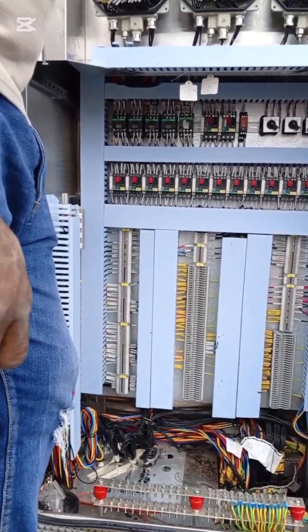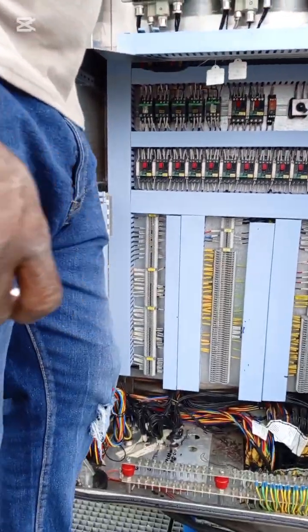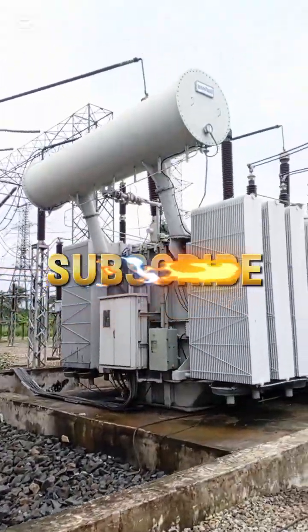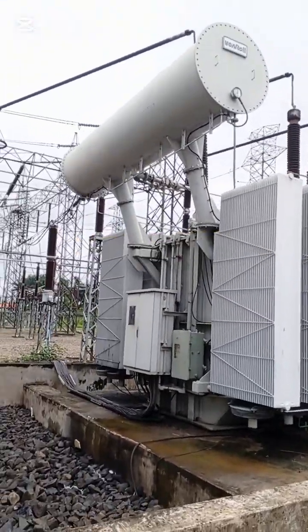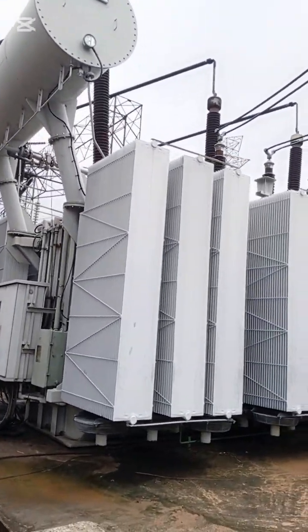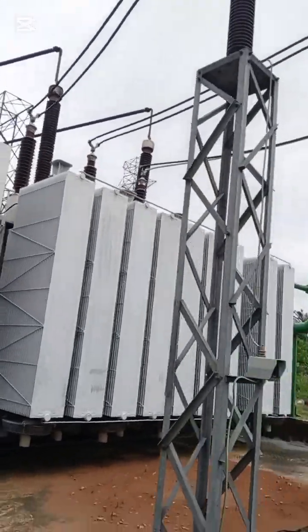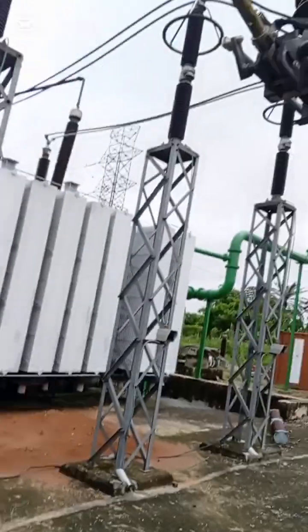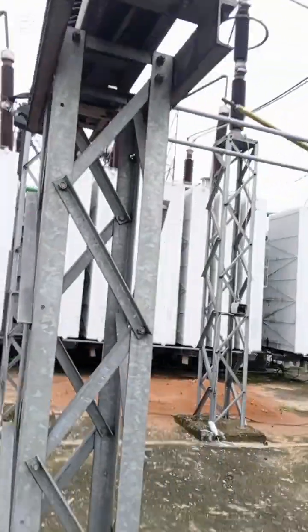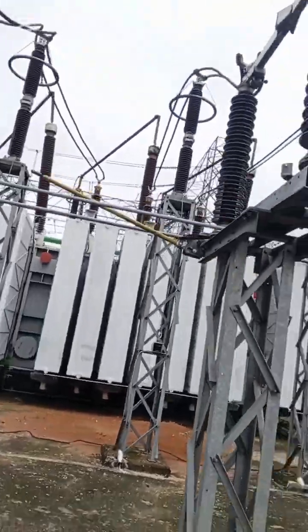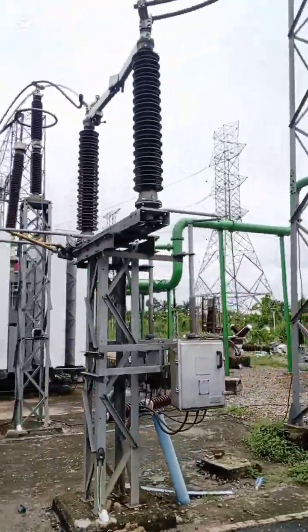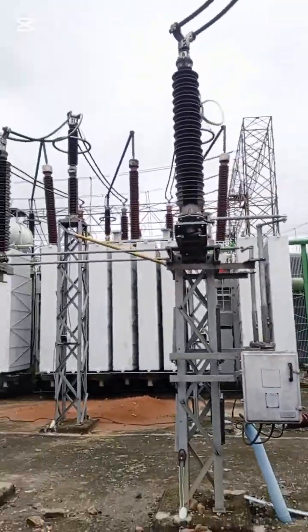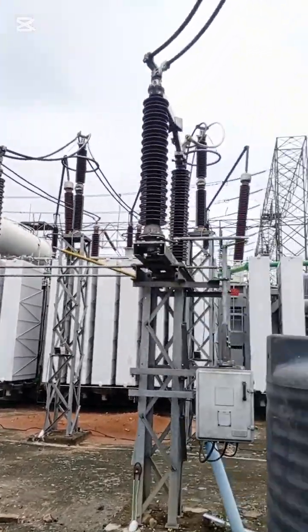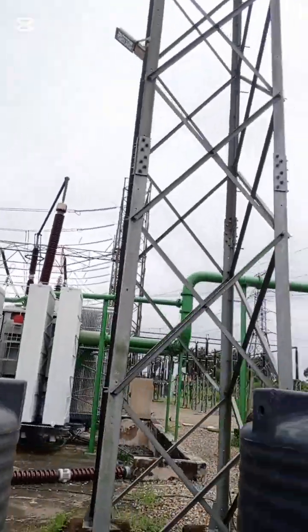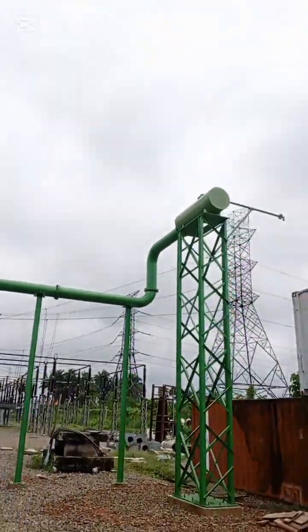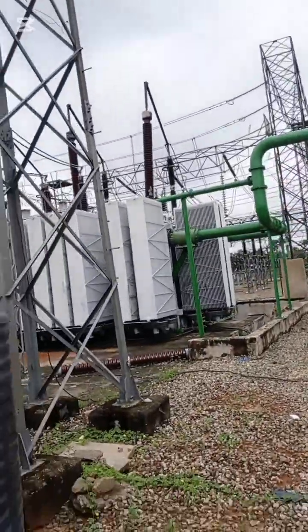3. Turns ratio test. Measures the turns ratio between HV and LV windings at all tap positions. Why it's important: confirms the nameplate ratio, verifies correct winding connections, and assesses the functionality of the on-load tap changer throughout its range. Deviations from factory values, usually 0.5%, are critical. 4. Vector group test. Confirms the phase displacement between the primary and secondary windings.